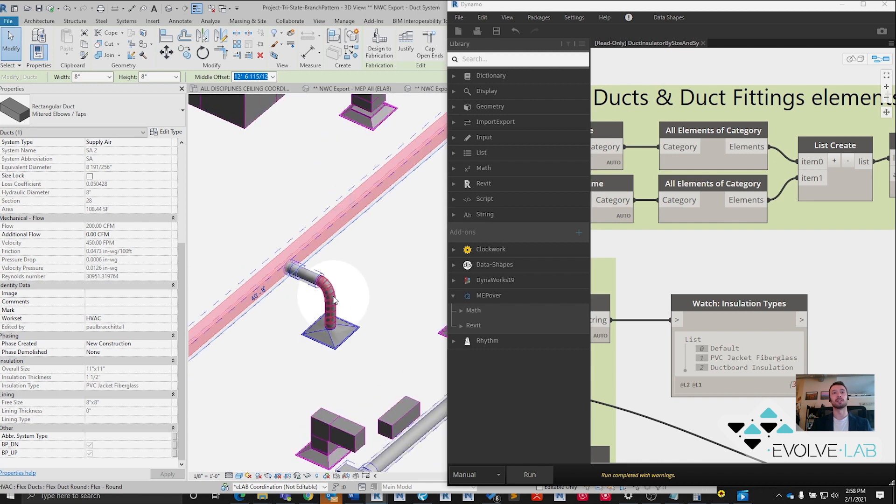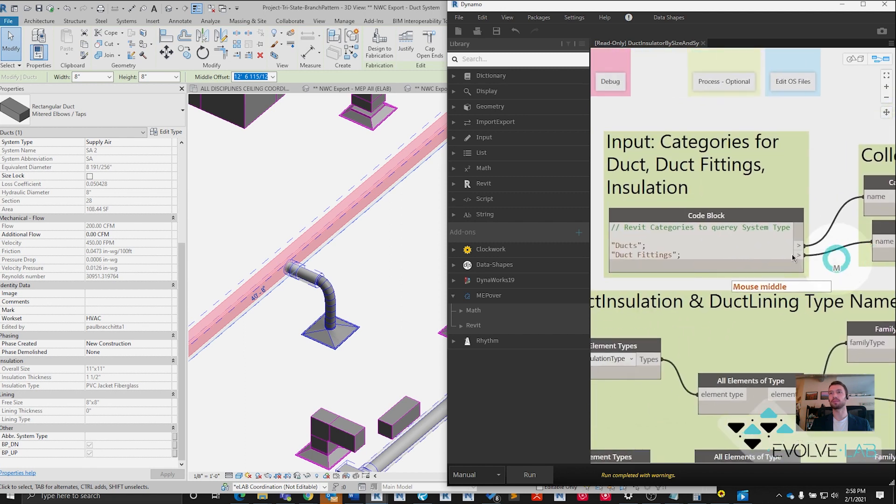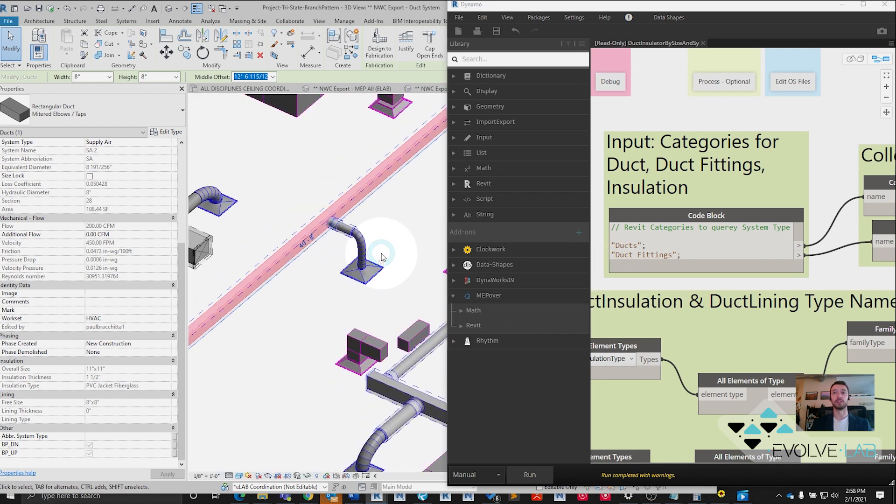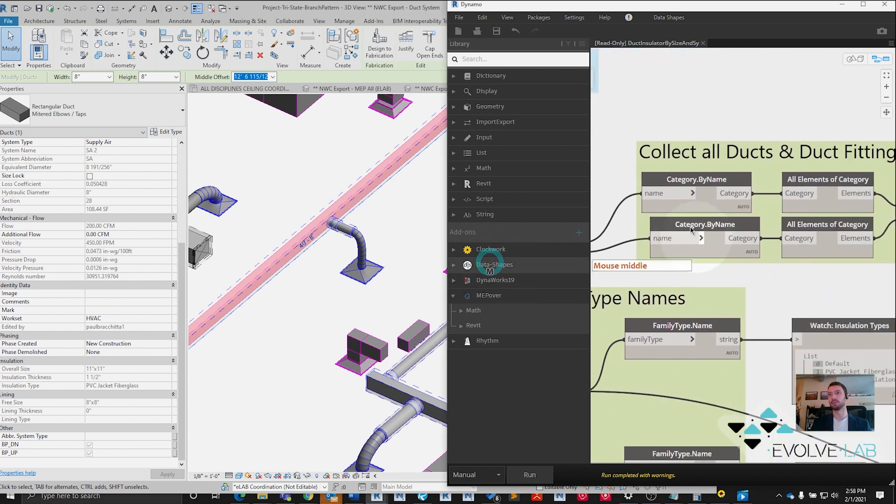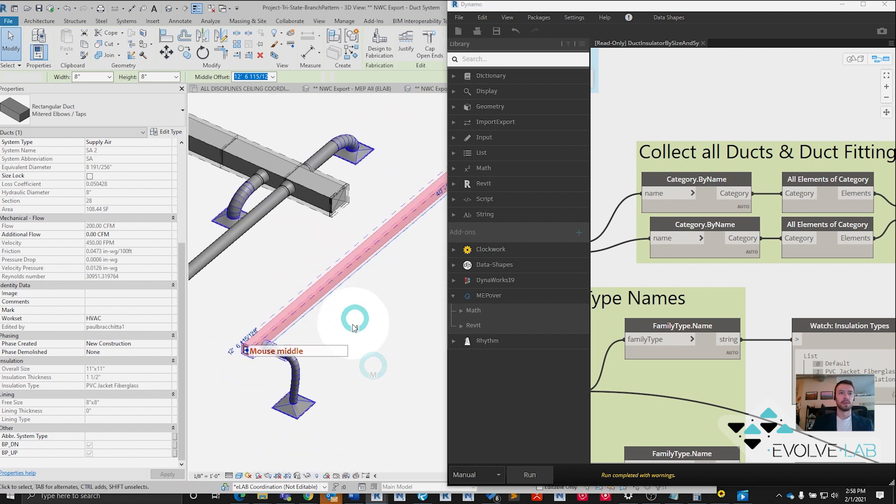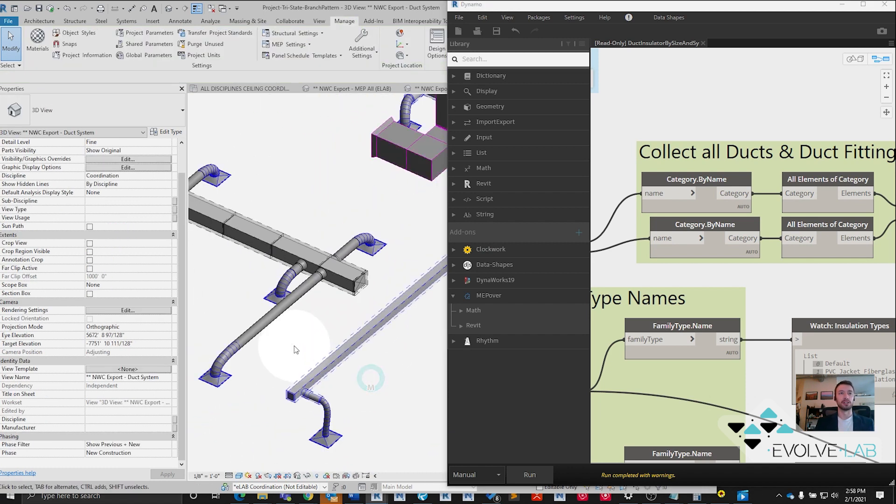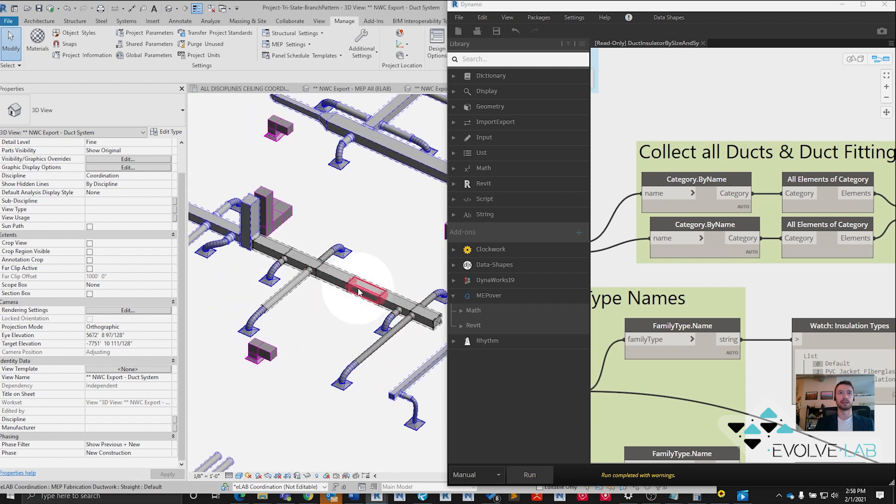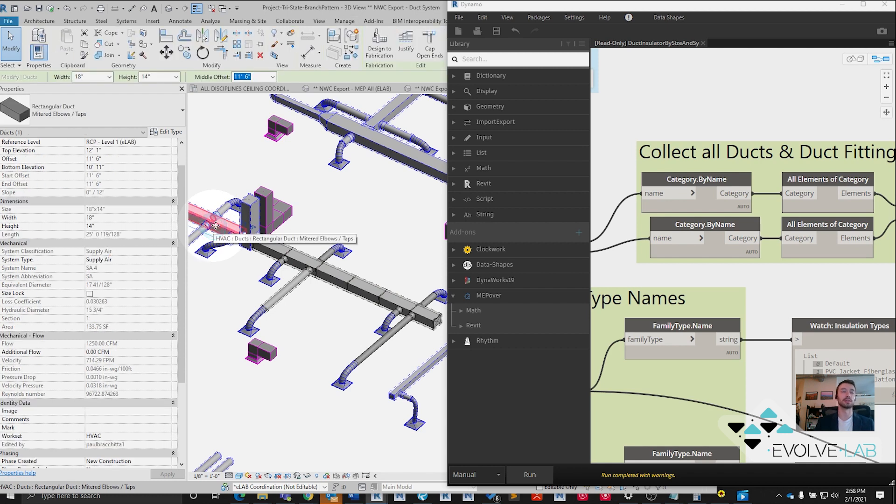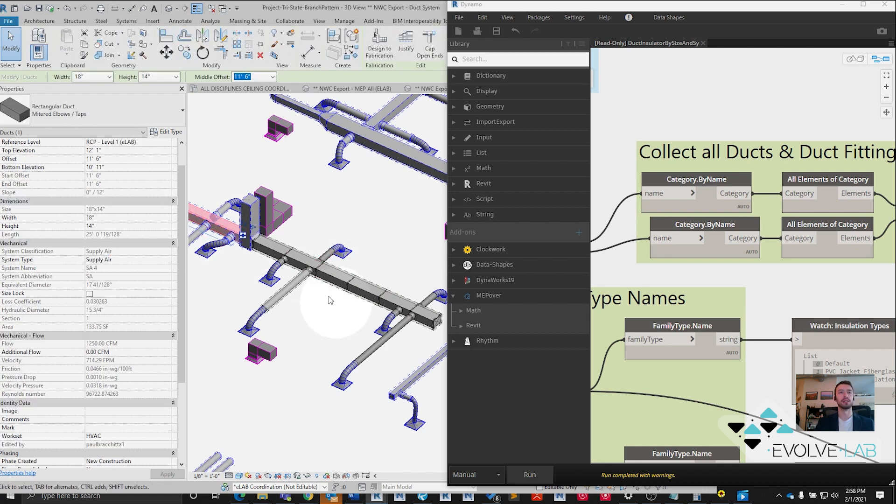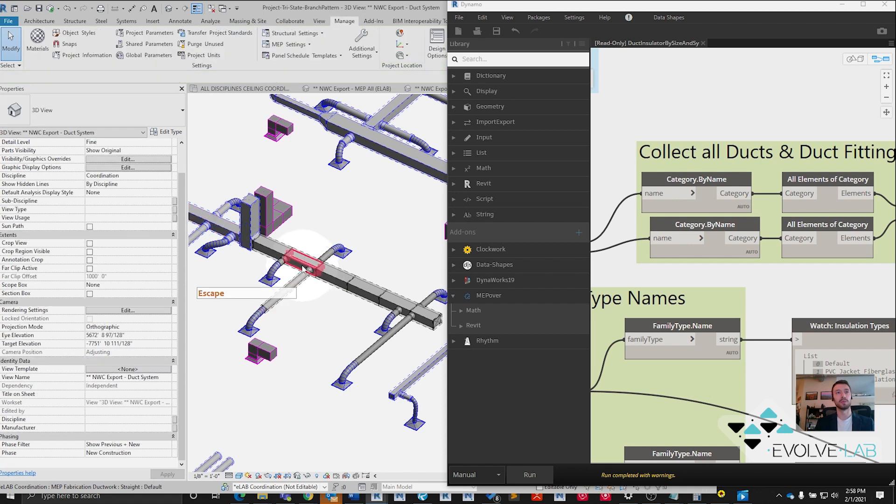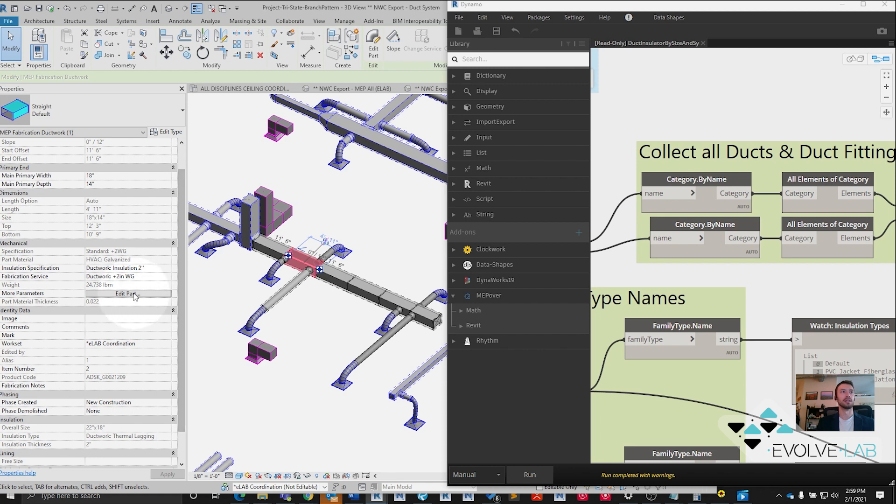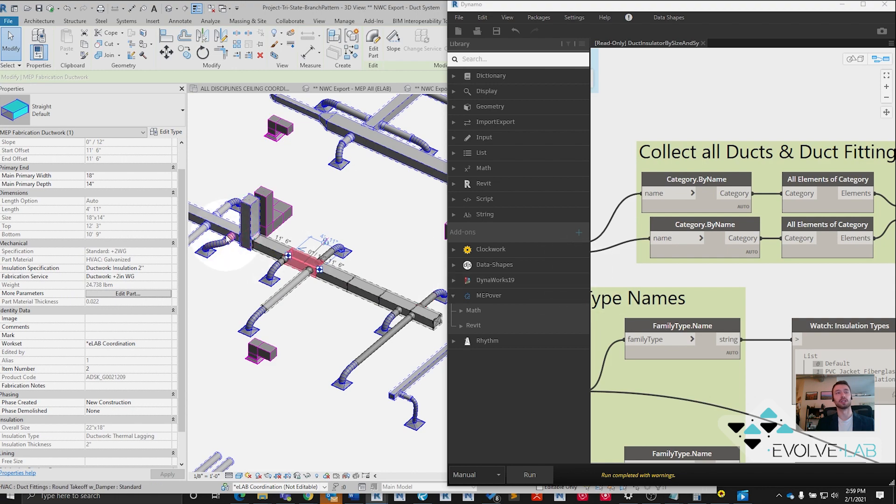I'm sure it's possible that we could add the flex air ducts to that collection list here. I do plan on creating a series of videos about this, so look for that in the future. Feel free to mess around with it too. Theoretically, it should work if you add flex ducts. Just one thing to note here about MEP fabrication duct, that's here in black, whereas all this other duct work, call it design duct, just the regular duct work system. The MEP fabrication duct work does not receive insulation from the script. It's a different system element, system family, system type. The insulation is all just different. So this script will work on design duct and not on MEP fabrication ducts.